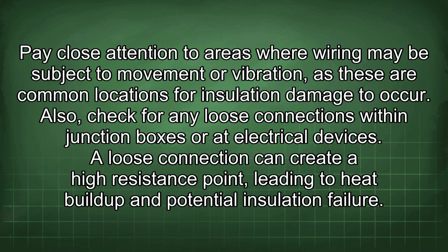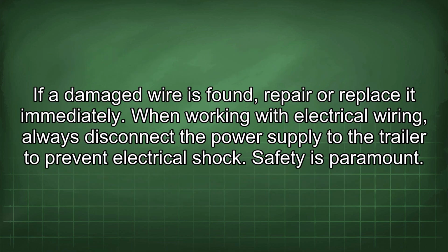Also, check for any loose connections within junction boxes or at electrical devices. A loose connection can create a high resistance point, leading to heat buildup and potential insulation failure. If a damaged wire is found, repair or replace it immediately. When working with electrical wiring, always disconnect the power supply to the trailer to prevent electrical shock.